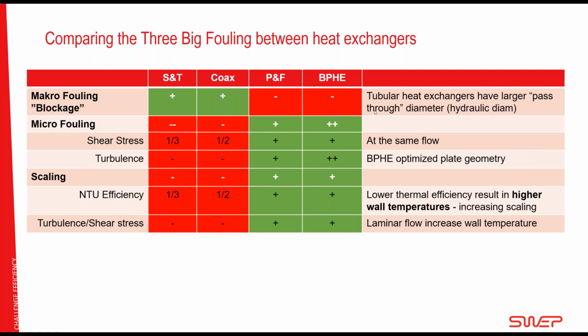That is why we continue to recommend a strainer. Put a strainer, so you don't get your port area clogged up. When it comes to microfouling, the suspended solids, I would say that the shell and tube is the worst one there, because it's designed with the baffles and everything. There are clear areas of dead zones where you will have buildup of fouling immediately. A lot of tests show that.